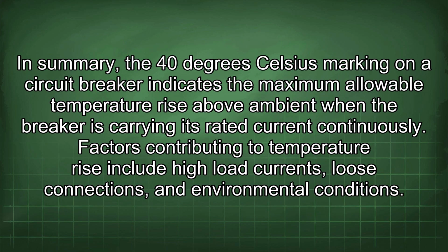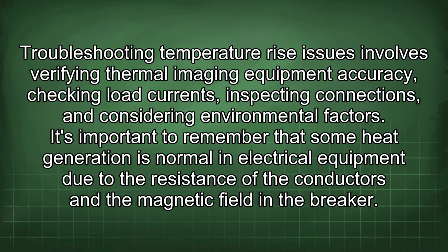In summary, the 40 degrees Celsius marking on a circuit breaker indicates the maximum allowable temperature rise above ambient when the breaker is carrying its rated current continuously. Factors contributing to temperature rise include high load currents, loose connections, and environmental conditions. Troubleshooting temperature rise issues involves verifying thermal imaging equipment accuracy, checking load currents, inspecting connections, and considering environmental factors.